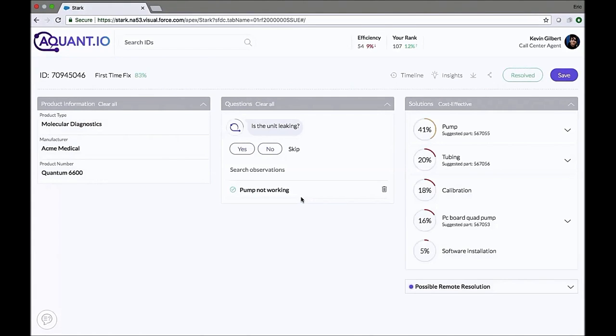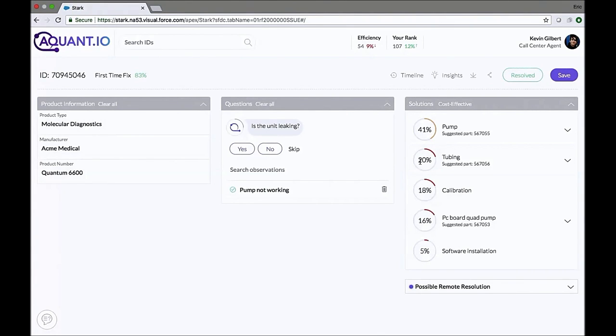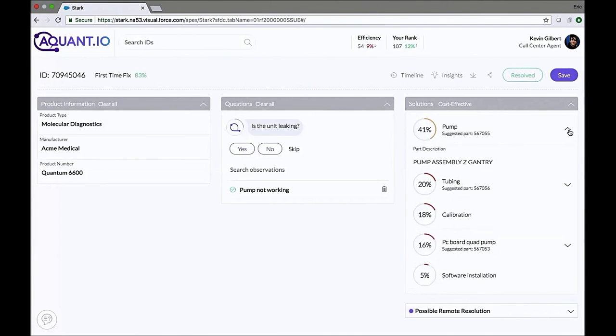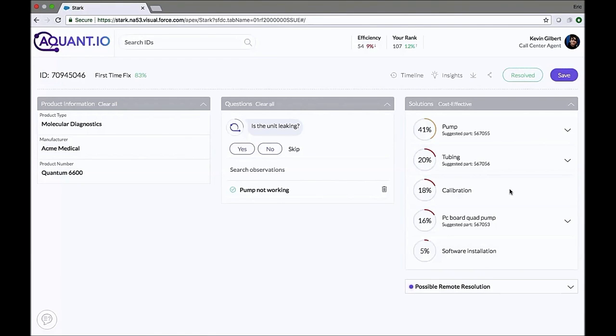Now I want to take a quick second to highlight a few things, simply based on one observation. The system already gave us some recommendations. There's a 41% chance we need to replace the pump. And by the way, 567055 is the part ID of the pump that matches the Quantum 6600 machine. There's a 20% chance we need to replace the tubing. 18% all we need to do is calibration. Now, this is a soft solution that doesn't require any parts replacement and came directly from the technician's comments in the field.